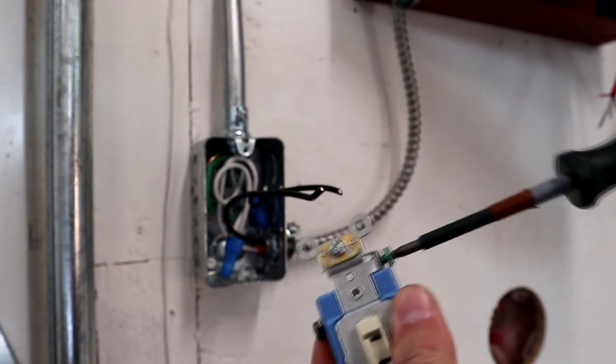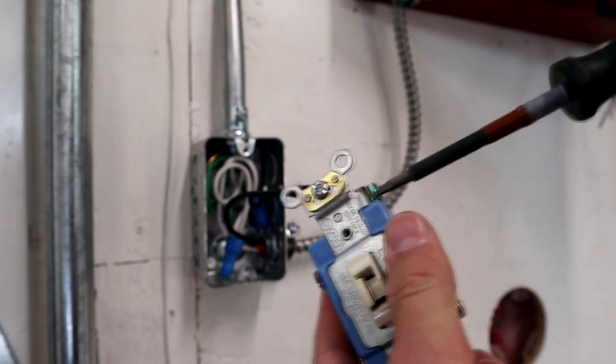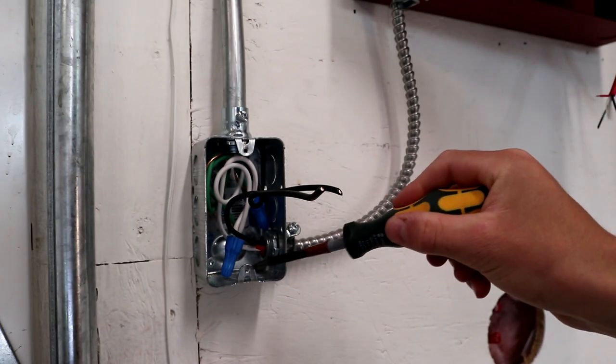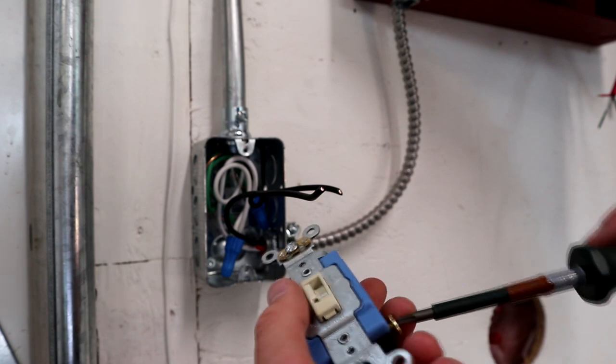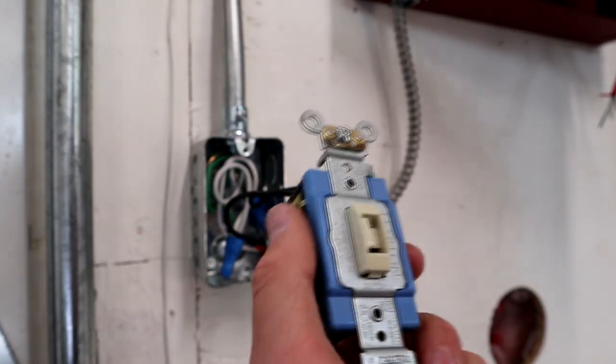Now we're just going to tighten the terminals that we know we don't need. I am in Canada, so we do not need ground on our switches because all of our boxes are bonded. Even our plastic boxes in Canada do have a bonding strip that goes from the back up and around that bonds the switch through its screw. You can use it, there's nothing wrong with doing that, but you don't have to. We won't need this traveler wire right here, so we can put this one in.